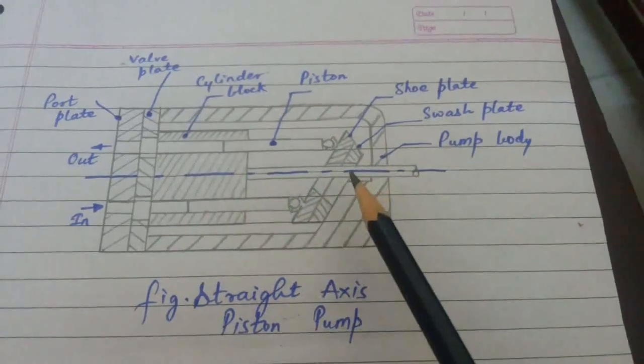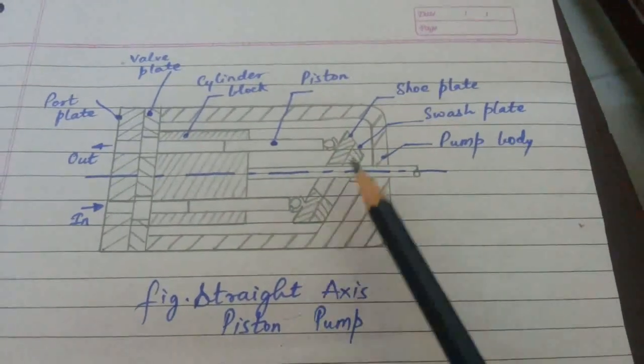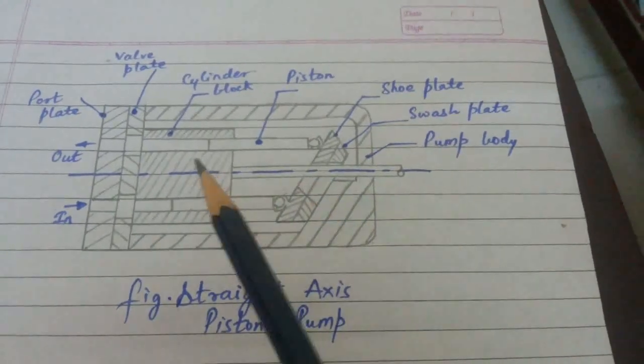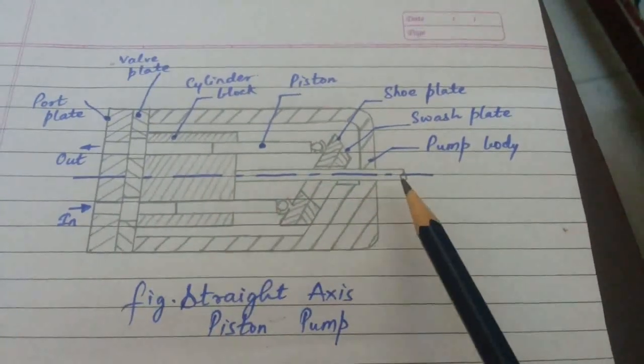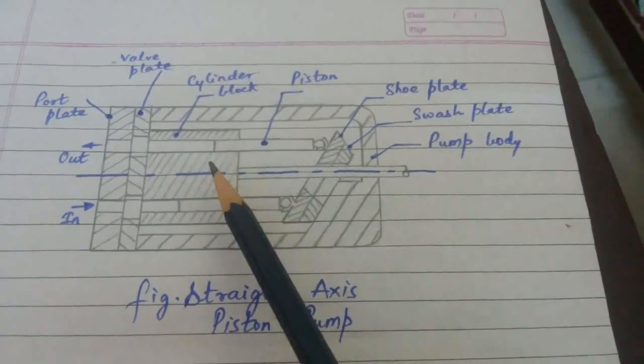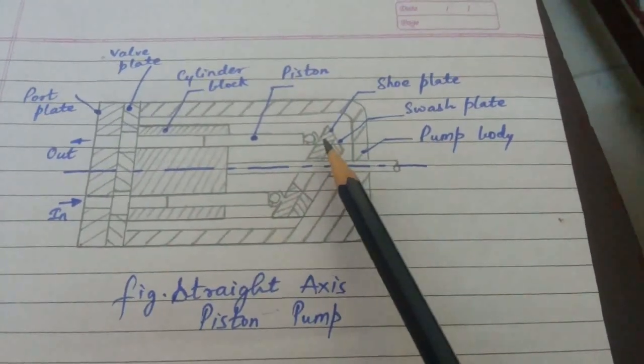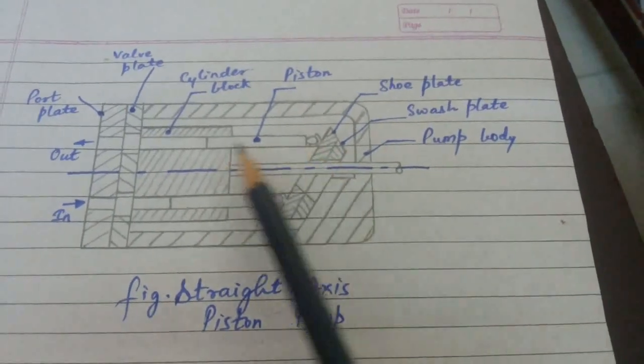And the shoe plate is mounted on the swash plate. The swash plate is at an angle, if we compare it to the axis. If we change the swash plate angle, then the discharge will change. When the shaft is rotated, then the cylindrical block is rotated. So the shoe plate is rotated. And that's why the piston is moved in and out.